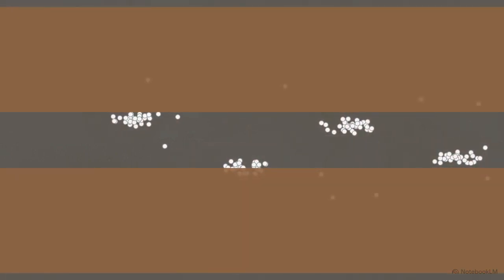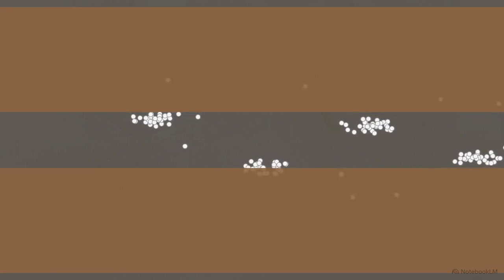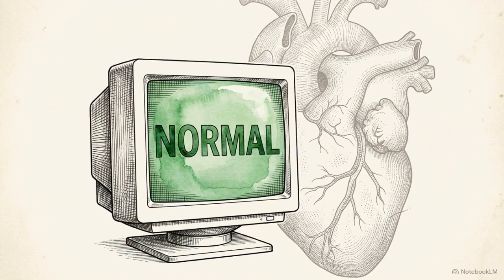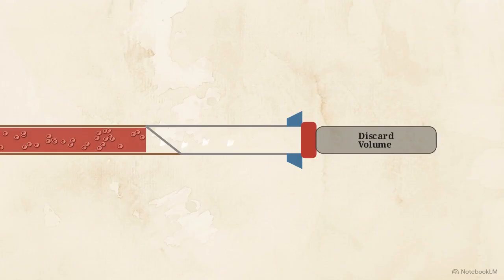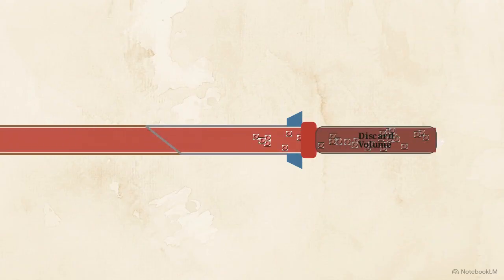Because red blood cells naturally sequester triple the selenium concentration of the surrounding plasma, those ruptured cells flood the sample. The analyzer will read a falsely elevated concentration, completely masking an underlying deficiency. To prevent this, clinical teams must draw the sample flawlessly into specialized, trace metal-free royal blue top tubes, often executing a strict discard volume just to flush out microscopic metal shards sheared from the needle itself.